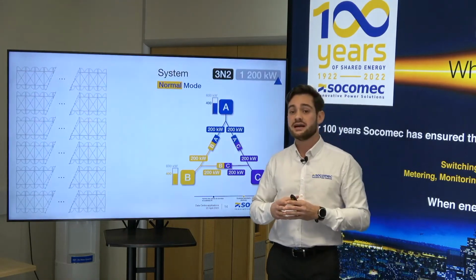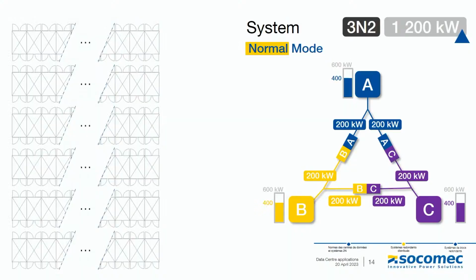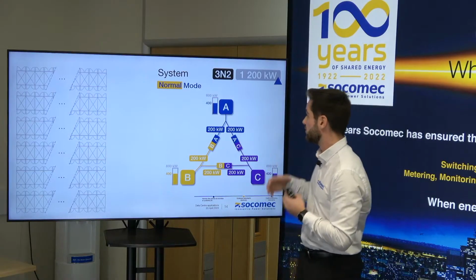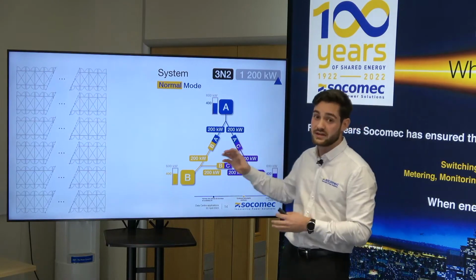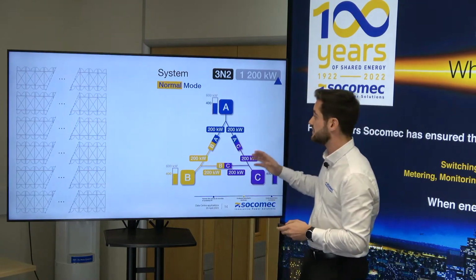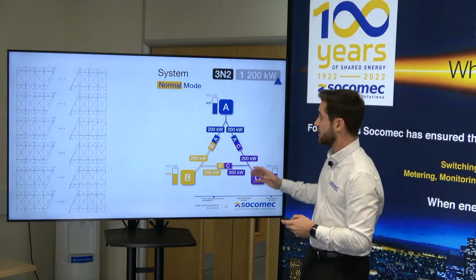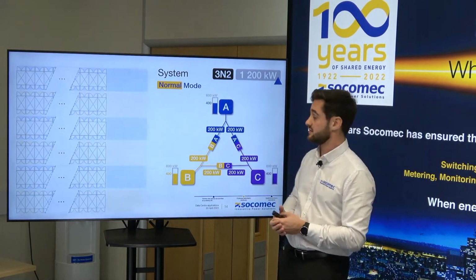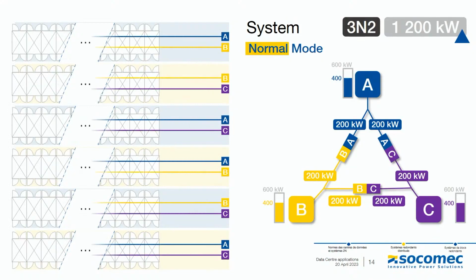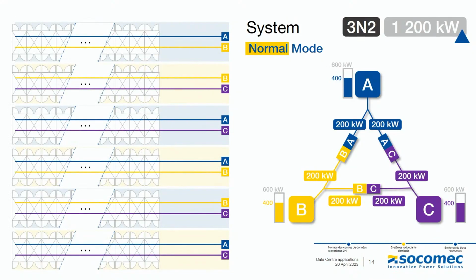Now let's have a look at an example. So now we've demystified these configurations. Let's pick up the 3N2 example. So we said we've got 1200 kilowatts. For this, as we've seen, we need 3 UPS systems, each one rated at 600 kilowatts, for a total of 1800 kilowatts. So in that case, even if there is a failure on one UPS system, we can rely on 2 other systems. So we've got system A, B, and C.